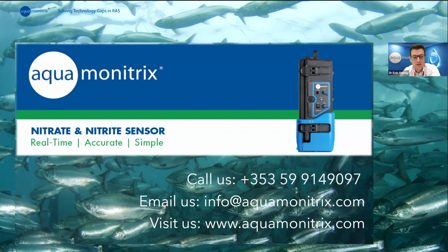It doesn't need to be recalibrated after regeneration of a column, or in fact, if we replace it with a new column, it still doesn't need to be recalibrated, which is a big advantage. We've tried to make the system as easy as possible to maintain and to install. Calibration is a big challenge for some other competitor systems, which we've tried to allow for and factor in.